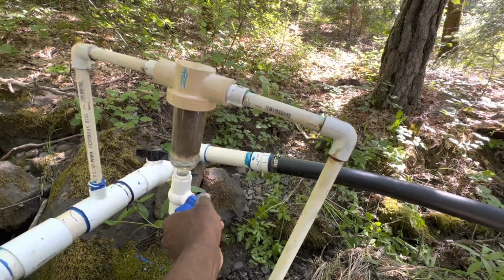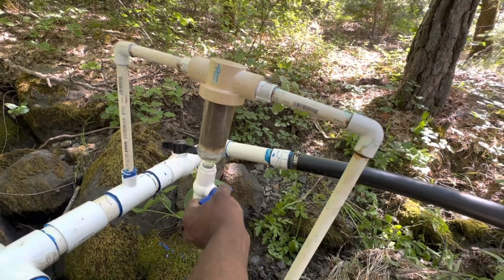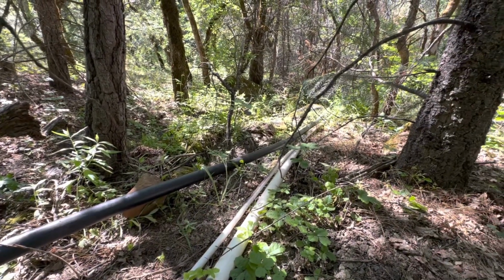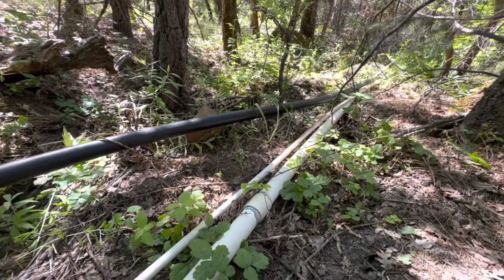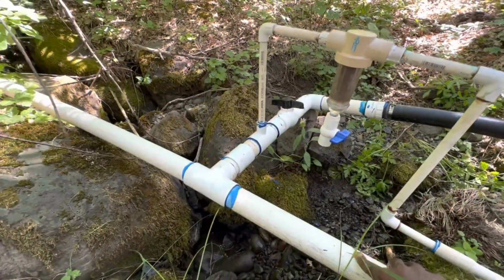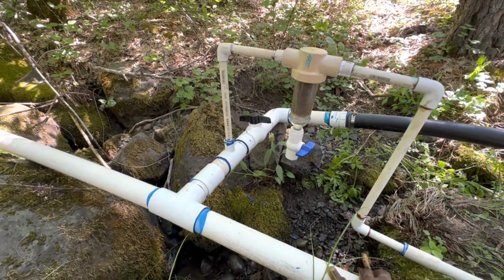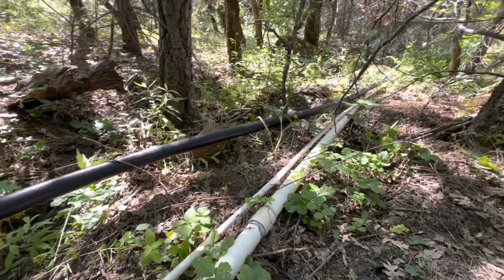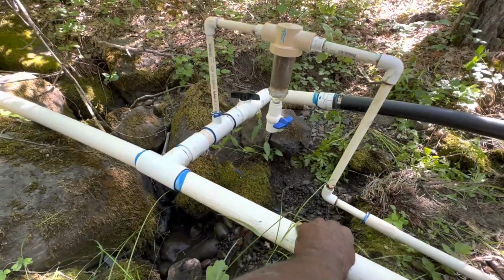Basically, when you turn the gate valve like that, you can basically spin off any sediment, and then you turn it off and the water keeps flowing down to the tank. And you'll notice that there is a 3/4 inch, and it reduces down to a 1/2 inch down there. But there's also a 2 inch right next to it. It goes about another 20 feet. The reason for this 2 inch is that it's designed to catch sediment. Sediment is usually heavier than water, so it's going to keep going down. It's not going to tee off into this filter here many times, unless it's heavy sediment. Lightweight sediment will, but heavy sediment is going to continue going down because of gravity, and it'll get trapped here, and it's purged out at the end down there. So basically what I get here is kind of like the good water, the clear water.